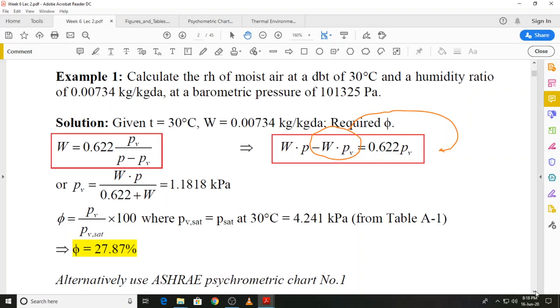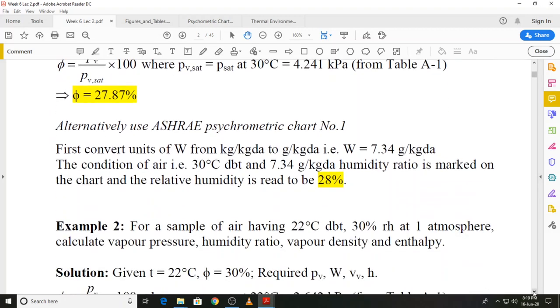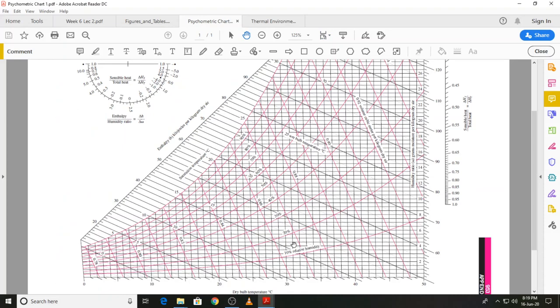We will now find the same result using the psychrometric chart. Note that the humidity ratio on the ASHRAE psychrometric chart number one has units of grams per kilogram dry air, so we need to convert the given humidity ratio from kilogram per kilogram dry air — multiplying by 1000 gives 7.34 grams per kilogram dry air. Let's now look at the psychrometric chart.